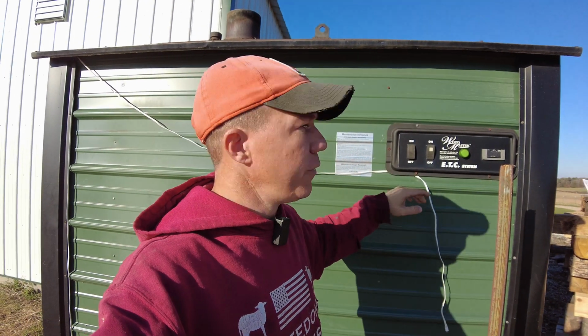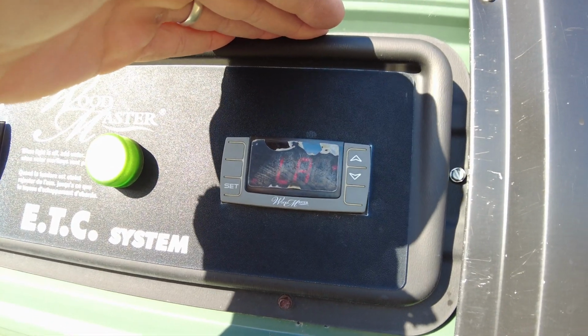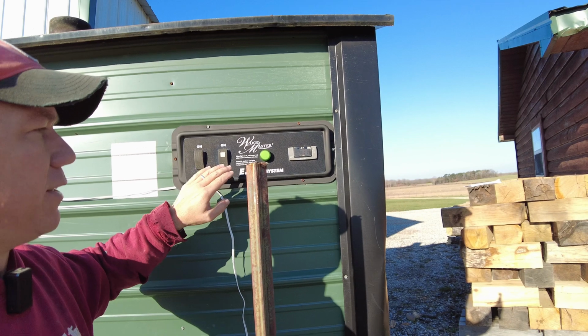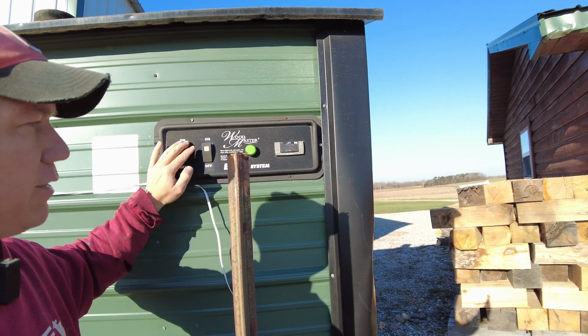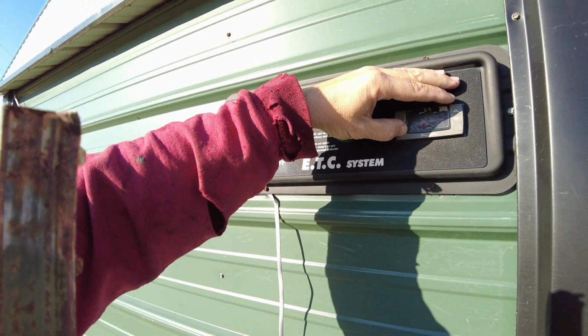So we set our temperature through this control. This is a Woodmaster 5500, the wood boiler itself, and this is the controller for it. It's a digital readout, and it'll tell me what the temperature of the water is. All right, so it's going to say LA because it's low alarm. So 61 degrees is what the temperature of that water is right now. Until we reset the low alarm, it will not kick the fans on. But let's say that I'm going to go ahead and fire it up. What I would do is hit set, and then it'll kick my fans back on.